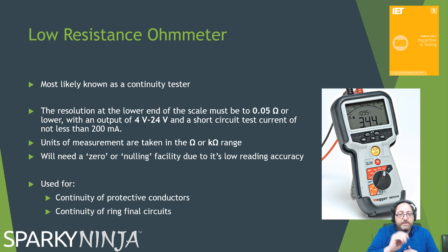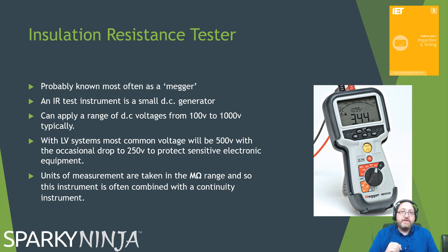So you set to ohms. The red section is your insulation resistance section. Still an ohmmeter, but this reads in the higher range. So the instrument changes to a little DC generator here, offering voltages of anywhere up to 1000 volts. I think this illustration here is 1 kilovolt. It's set on 1 kilovolt. We normally would use it on 500. I don't know why that's on 1 kilovolt. But the insulation resistance tester has a number of voltages, and it measures resistances in the megohm, which is the large M. Never write it down as a little m, that's the milli. Get your millis and your megas straightened out now. Sort that out now.